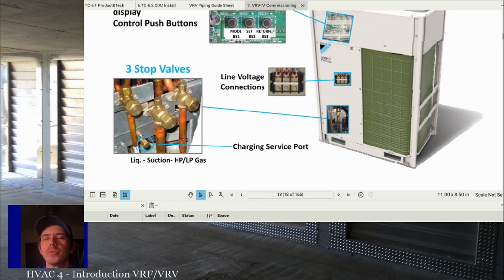So some units have an oil recovery mode that they go into to try and make the refrigerant move through the system at a rapid rate, to return all the oil back to the outdoor unit. Some of them, like if I remember right, Daikin, just have the way the system runs tends to return oil pretty well. So they don't have a specific mode that occurs, but the system has a way of making sure that the oil returns. But if you don't install the piping the proper size, or something like that. I'm trying to think of another example. Or if you have too many offsets in the piping or something like that, then the oil won't return properly.